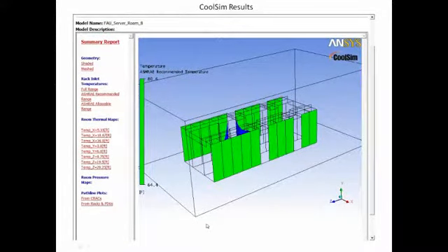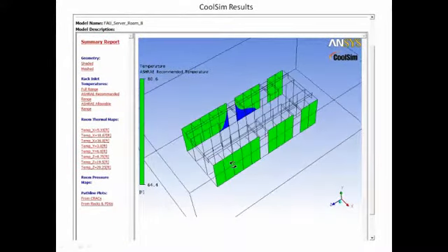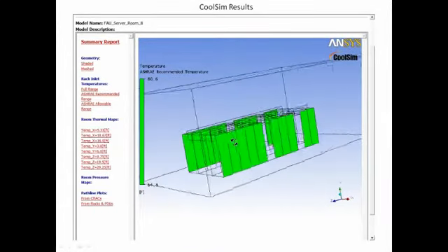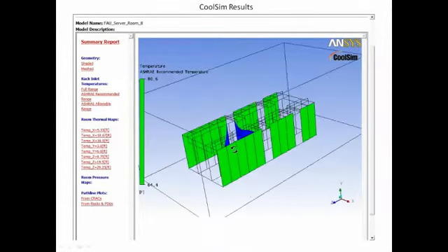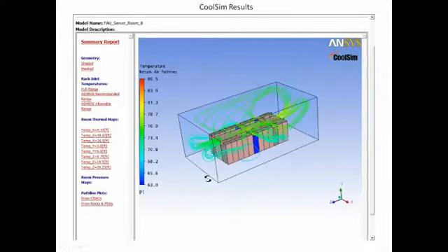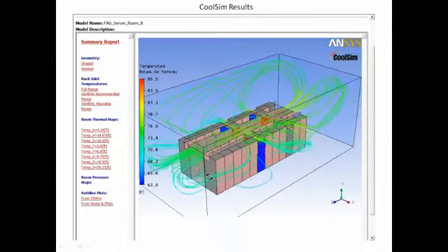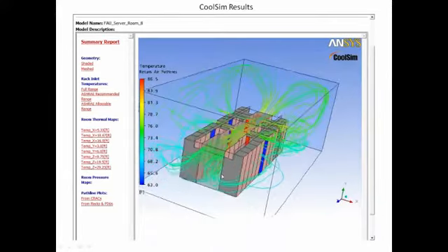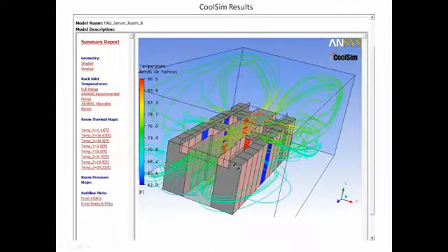And that's okay, but with only 3 CRACs on, the question becomes, what's its performance in an N+1 kind of configuration? What if I lost the power to another CRAC? And furthermore, what's going on here with respect to performance? And you see here that these racks are trying to recirculate around themselves. There are a couple holes, fortunately, in this system.